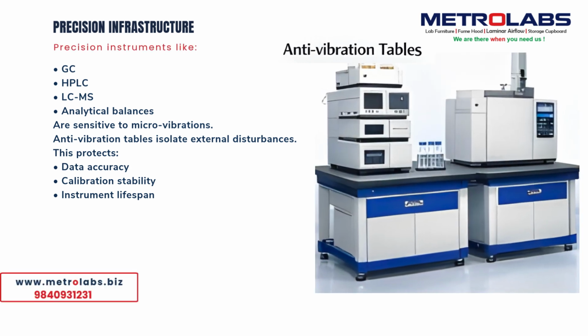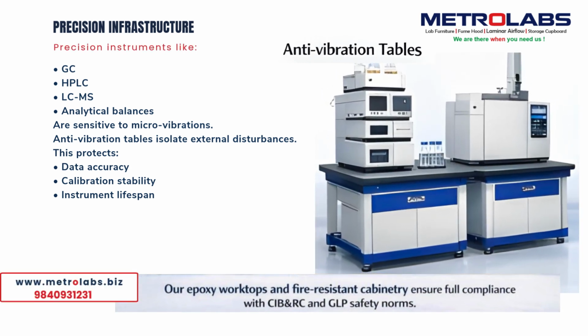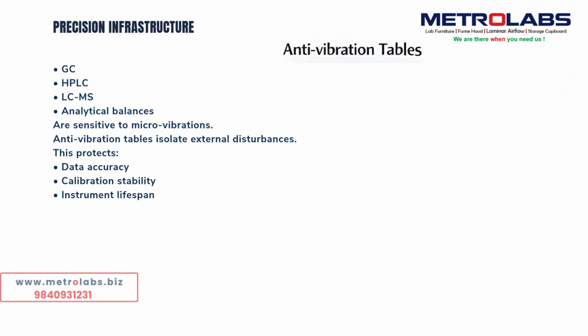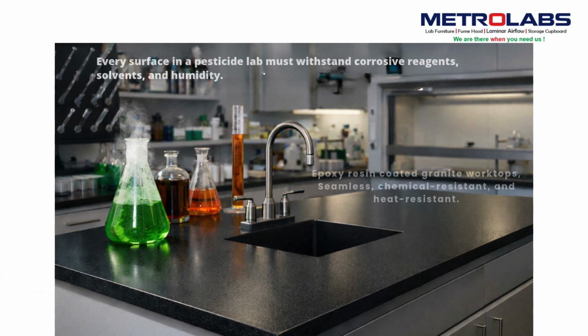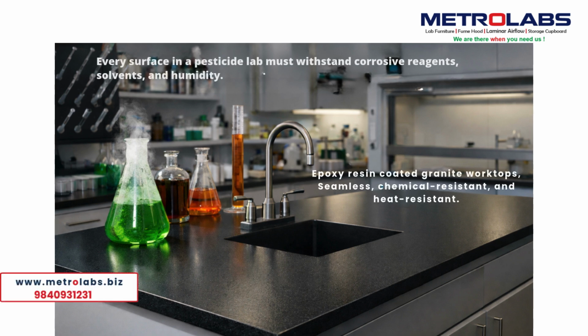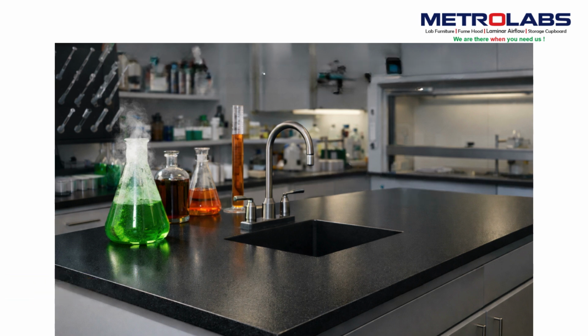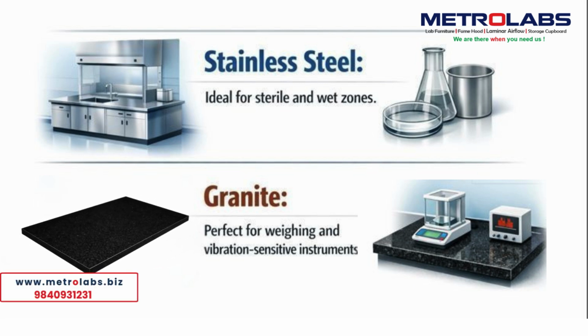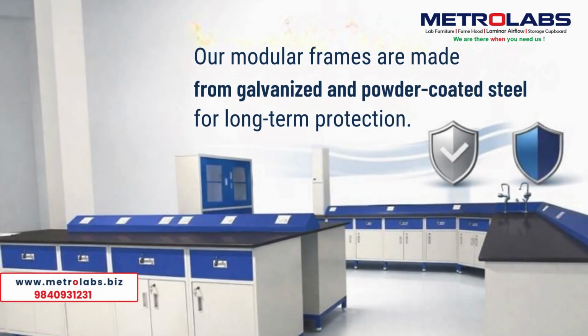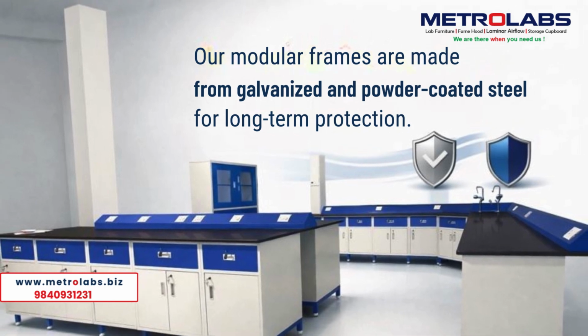Precision infrastructure. Precision instruments like GC, HPLC, LCMS, analytical balances are sensitive to micro vibrations. Anti-vibration tables isolate external disturbances. This protects data accuracy, calibration stability, instrument lifespan. This is not comfort. This is precision protection. Materials of construction. Every surface in a pesticide lab must withstand corrosive reagents, solvents, and humidity. That's why Metrolabs uses epoxy resin-coated granite worktops, seamless, chemical-resistant, and heat-resistant. Stainless steel, ideal for sterile and wet zones. Granite, perfect for weighing and vibration-sensitive instruments. Our modular frames are made from galvanized and powder-coated steel for long-term protection.